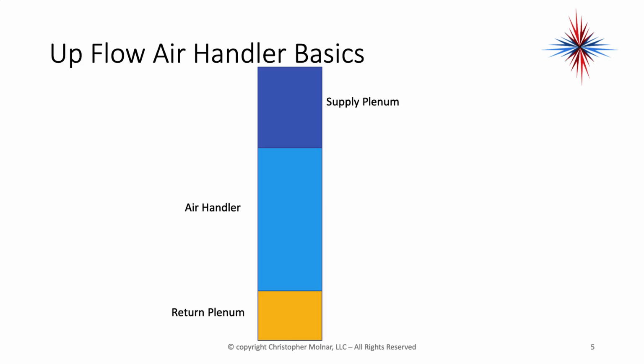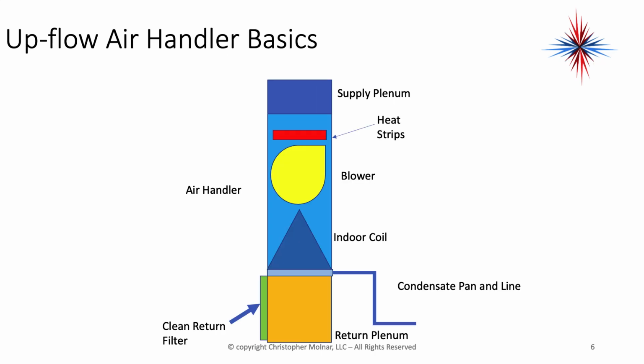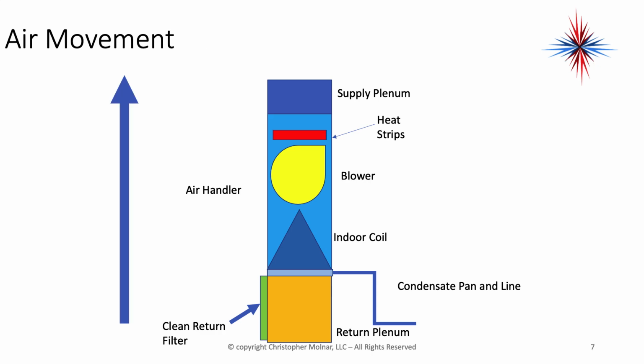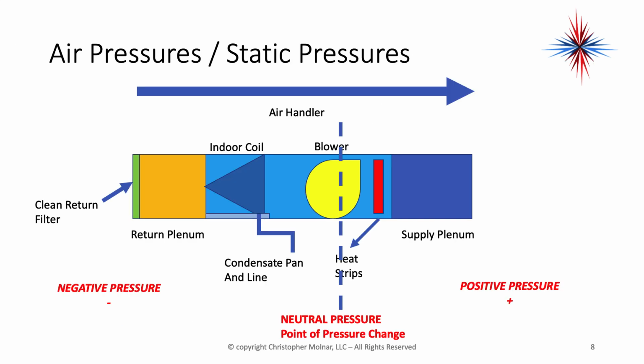If we have an upflow air handler, it's the same principle. Again, return plenum, air handler, supply plenum. We still have our indoor coil with the condensate pan and line. We have our blower, and we have our heat strips. Our filter is someplace before the return plenum. Air movement is up. That's why it's called an upflow furnace or an upflow air handler. Now, you'll find in some mobile homes, in some pre-manufactured housing, might be a downflow system, but I'm not going to cover that here because it's the same basic principle. Just the air goes in a reverse pattern, and the return plenum is on the top, supply plenum is on the bottom.